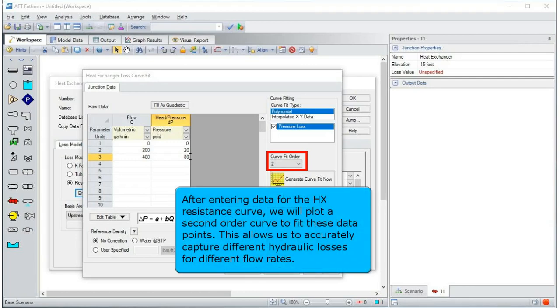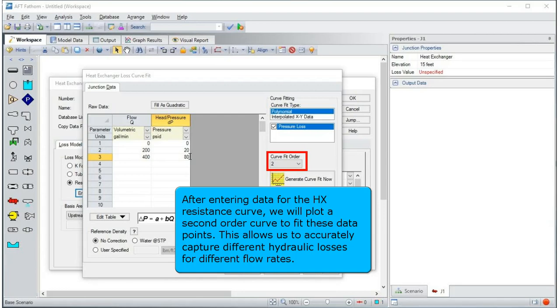After entering data for the heat exchanger resistance curve, we will plot a second-order curve to fit these data points. This allows us to accurately capture different hydraulic losses for different flow rates.